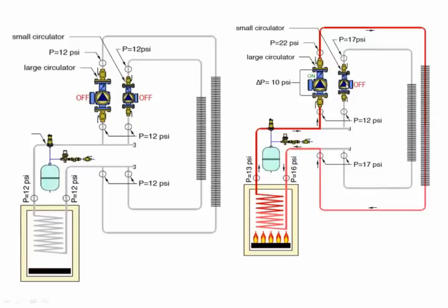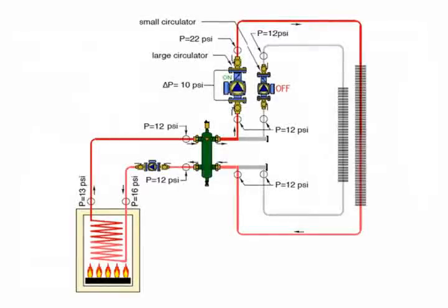Now there's going to be a call for heat on this second zone. But before there's a call for heat on the second zone, let's see what happened here. When we came back around here, we had 17 psi. We had to continue around. We got to here, we have 12 psi. 17 psi, 12 psi. We have created a 5 psi back pressure on this second pump that hasn't even fired on yet. And if that pump has been designed to deliver 3 psi head, guess what? It's not even going to be able to generate any flow. Okay? So that's a problem.